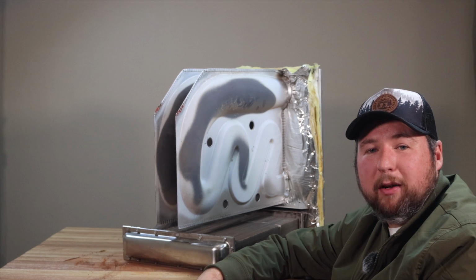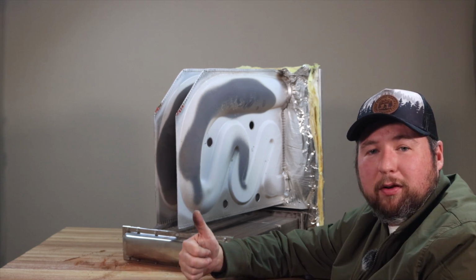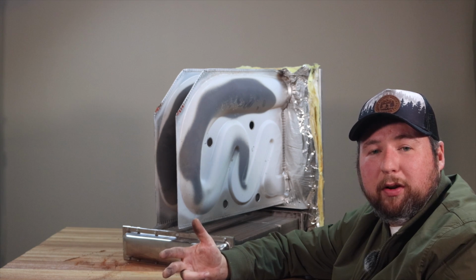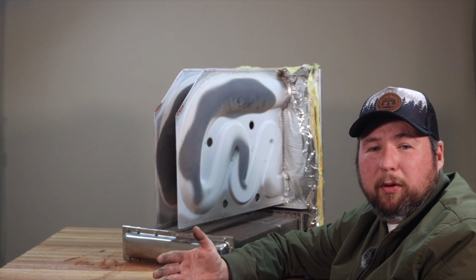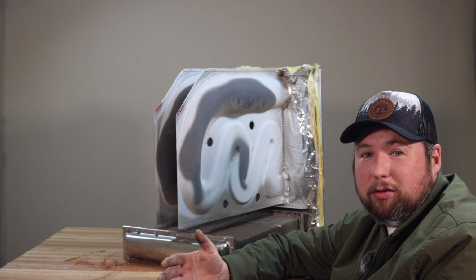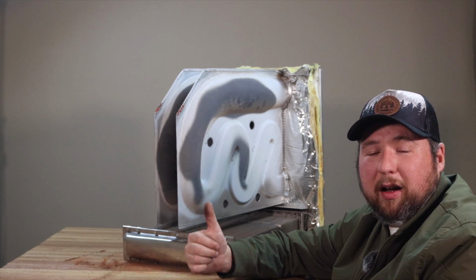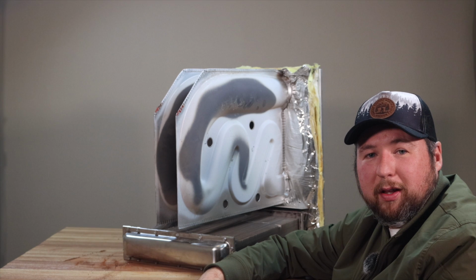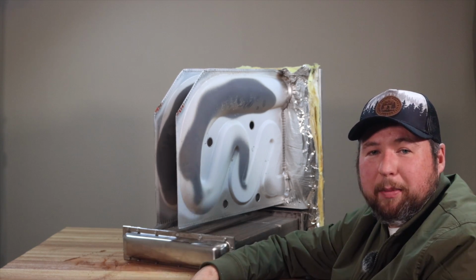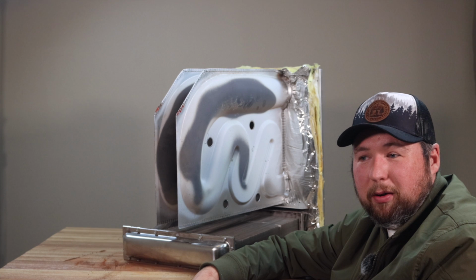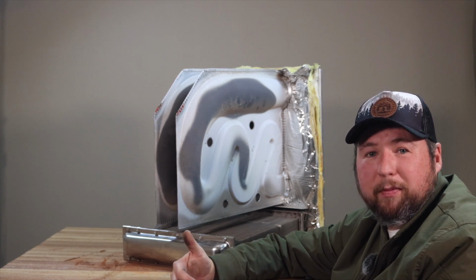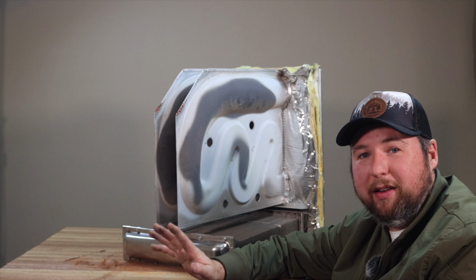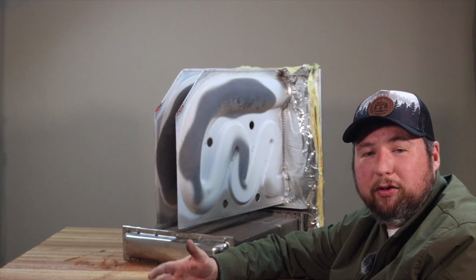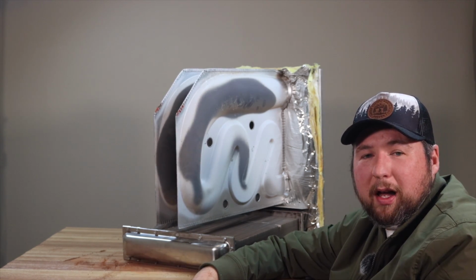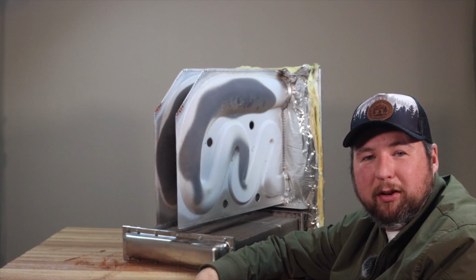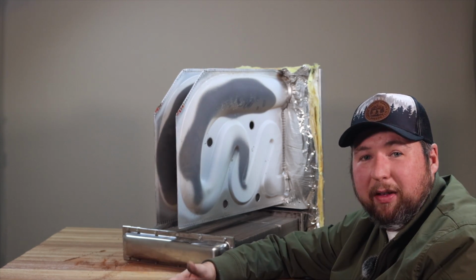And what are the things you want to be looking for? Check for dirty filters, check for bad blower motors, check for small returns, check for any kind of airflow restriction, whether it be the ducts are too small or something like that. That can cause a heat exchanger to fail prematurely. Because like I said, these things will usually last about 10, 20 years. There's still some natural draft furnaces out there that are 40 years old, not a single crack in that thing. Unfortunately I didn't have a clamshell heat exchanger to show you. But hopefully the charts kind of help you understand what they look like and how they work.